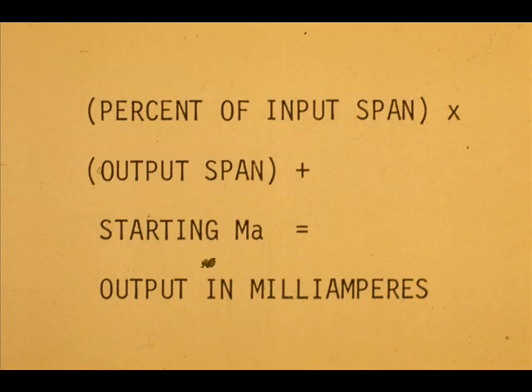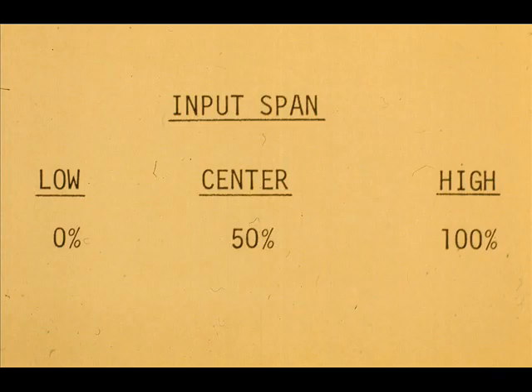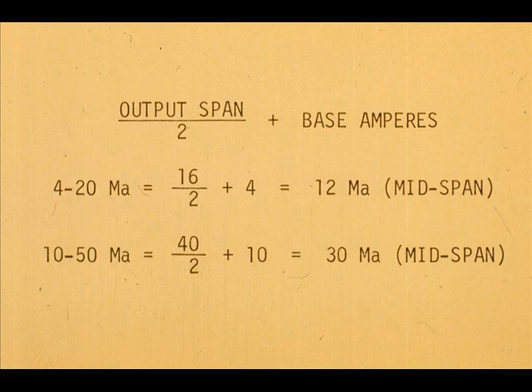In summary, this expression explains the mechanics of calculating the output for either the 4 to 20 or 10 to 50 milliamp range. For any transmitter, there are three outputs we should know using only mental calculations. The 0 and 100 percent span outputs are obvious. For the mid-span output, divide the output span by 2 and add the base or starting current.